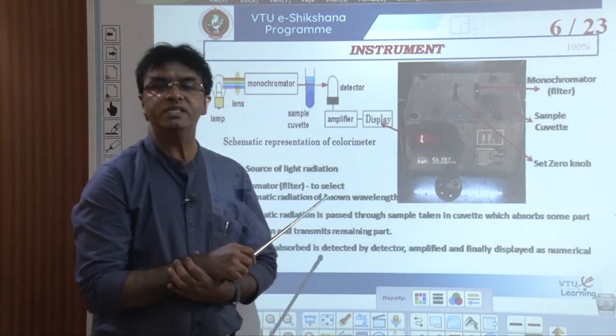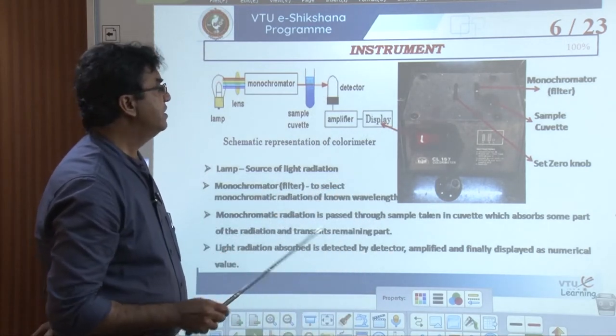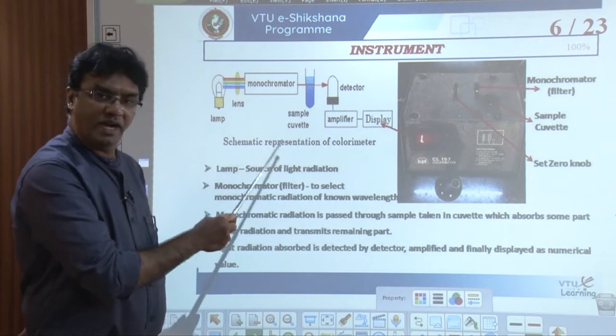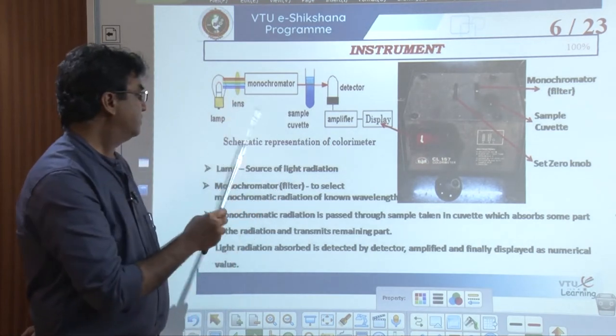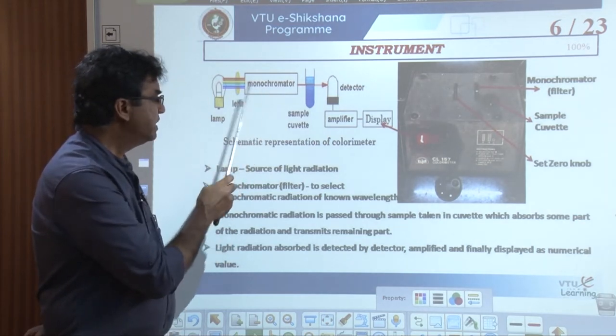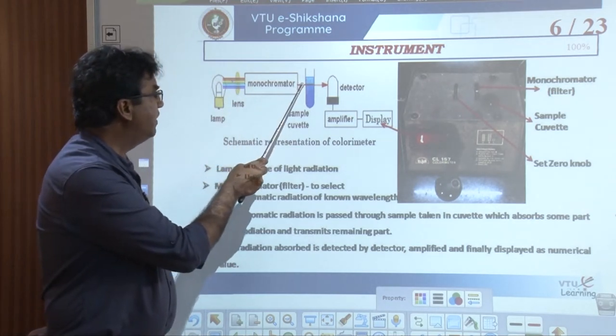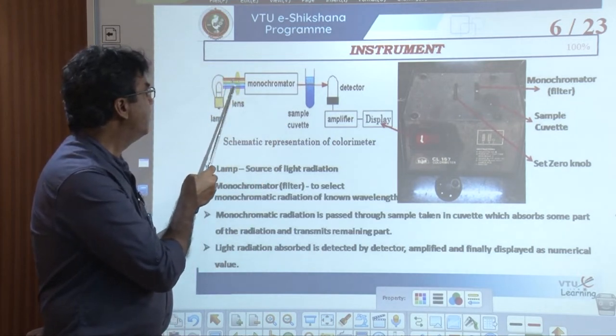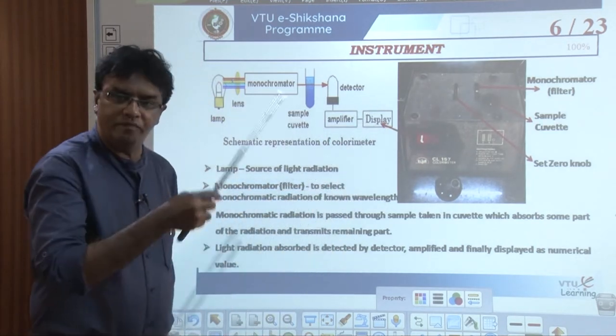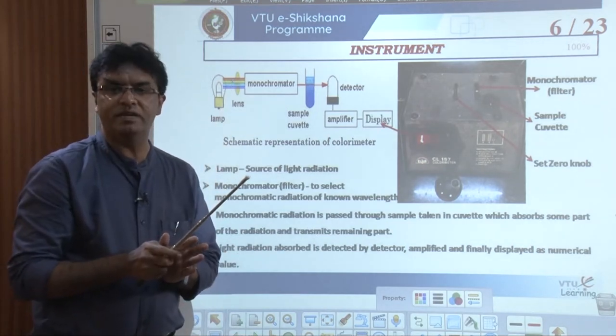Coming to the instrumentation — this is a photograph of the colorimeter, which consists of several parts. There is a lamp that produces a beam of light, and that beam is passed through a monochromator, also called a filter. The filter selects the exact wavelength required. For example, if a wavelength of 560 nanometers is needed, the filter filters out all other wavelengths and allows only light of 560 nanometers. A beam of light is a combination of various wavelengths.